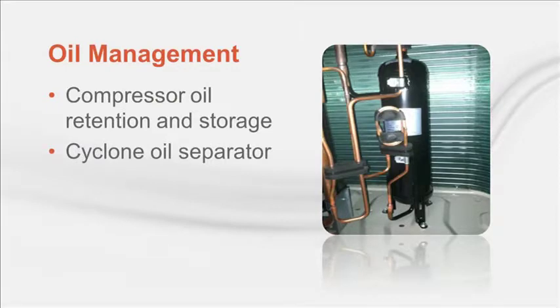Next, the addition of an oil separator helps capture most of the oil that is pumped out of the compressor and is injected back to the compressor. Yet since the separator isn't 100% effective, some oil will still circulate out in the system. So VRF systems have a built-in oil recovery cycle, a flush cycle if you will, which is initiated based on compressor runtime, frequency, and other factors. When the oil recovery cycle begins, an expansion valve will open to a minimum setting and the compressor will speed up to flush the oil back to the compressor in the outdoor unit.